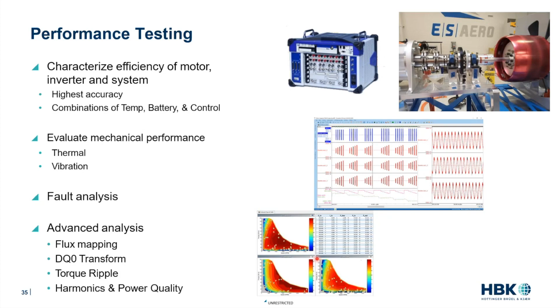And then for the motor control nerds who might be tuning things to reduce noise, to reduce vibration, we can look at the DQ0, the torque ripple, harmonics, power quality, do things like efficiency mapping. So we have a really nice package for doing that motor analysis.